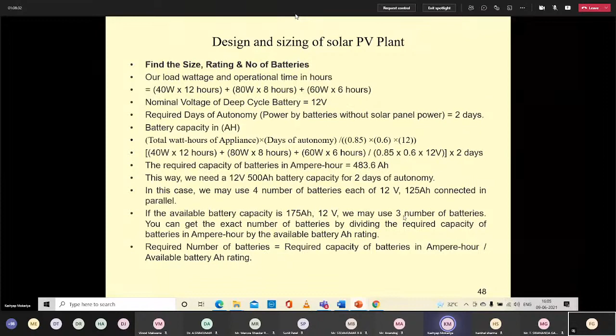So I prefer a higher rating than this which is available in the market. So I will get a 12 volt 500 ampere hour battery capacity, but when I visited a site, I didn't get a 500 ampere hour battery. So while adding capacity to reach 500 ampere hour, we connected four 125 ampere hour batteries in parallel. If the available battery capacity is 175 ampere hour at 12 volt, then obviously instead of 4 we can get 3 batteries for the same rating. Required number of batteries is equal to the required capacity of battery in ampere hour divided by the available battery rating.